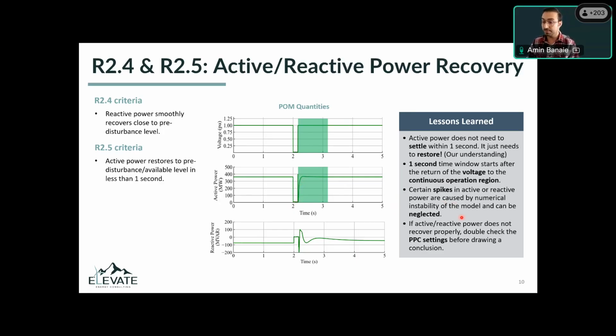And another factor that I've seen specifically in PSSE and PSLF are certain spikes that you may see in active and reactive powers, like this one here or this one here. Spend some time on these spikes and make sure that these are real spikes, because again, when the voltage is 0, PSSE and PSLF engines may face some numerical issues in terms of solving the equations in the circuit. So you want to make sure to see if these spikes are actual and real, and maybe you can check that with EMT models. That's a good approach, or if you see that in MQT reports of the plant. Also, if you see that active or reactive powers do not recover, double check the PPC settings, because that's the one which is in charge of active reactive power recovery.